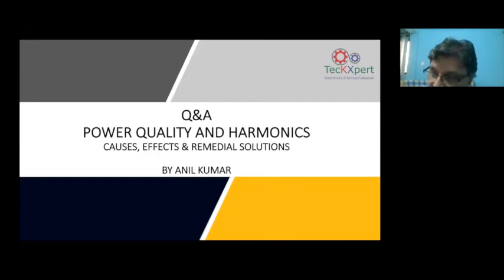So, do you suggest that a harmonic test is mandatory as part of a safety audit in a year or something like this? Will it be helpful? It will be. See, this is not just a harmonic audit; it's a power quality audit. In a hotel scenario, there are a couple of aspects. One is how much wattage loss is happening across the network, because your reactive current, active current, and harmonic current, all three currents increase the wattage loss in the network. And in some critical areas, these wattage losses can be so high that they can deteriorate the insulation over a period of time, and it can cause fire and those issues.